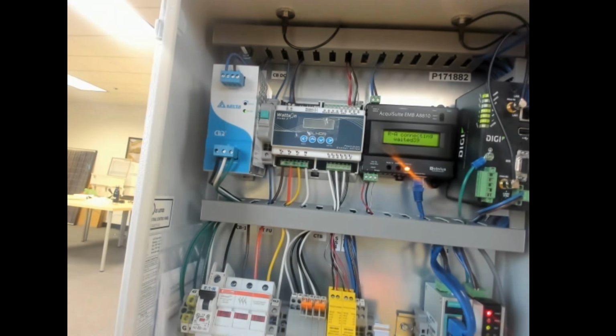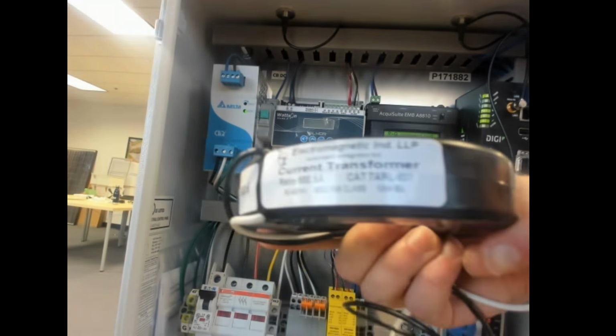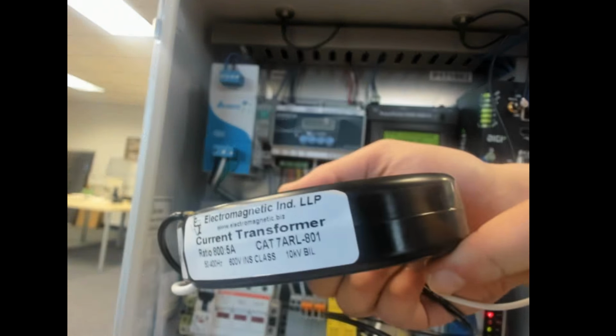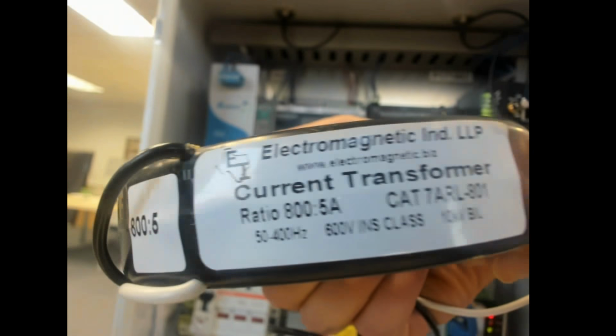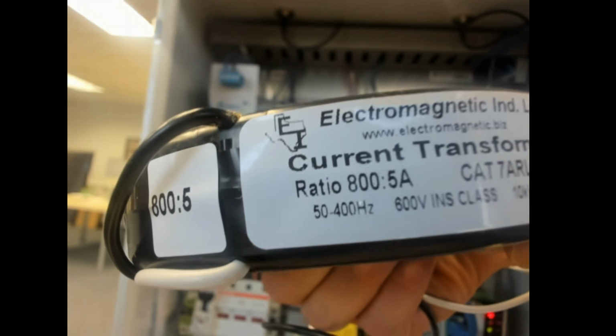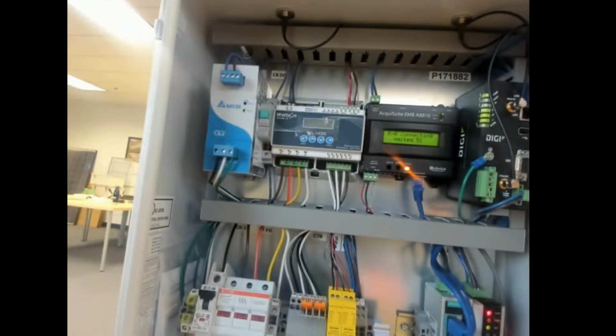When we're looking at a 5 amp CT, it'll actually have a current ratio. So here we have a 5 amp CT, and the label clearly says 800:5A. So if you guys are working in the field now, especially since technically we can work with a millivolt CT or a 5 amp CT - we have for a while, but it's going to be even more prevalent now.